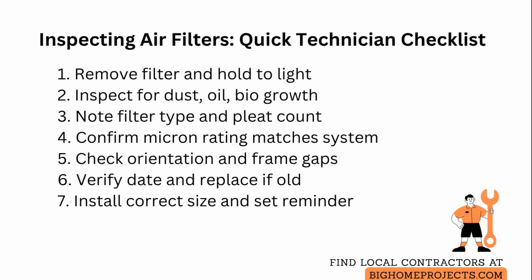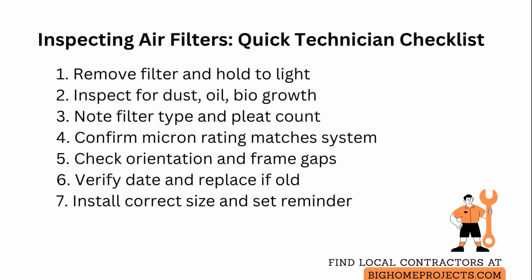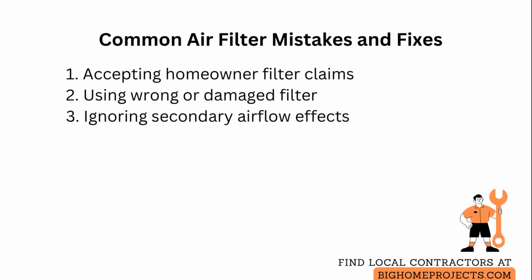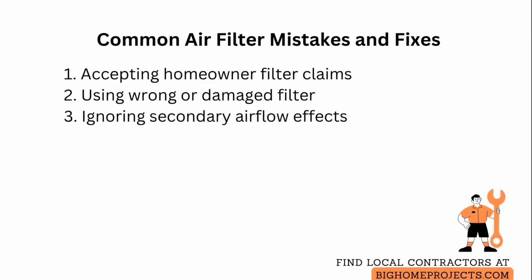When replacing, install the correct size and a filter rated for your intended airflow, and advise the homeowner how to mark a date and set a simple reminder to prevent repeat problems. Common mistakes include accepting the homeowner statement that the filter is clean, which leads to missed contamination or misdiagnosis. So always inspect and document the actual condition.